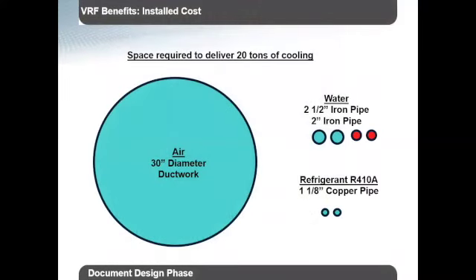So we think about, how is this possible? How is it possible that VRF can really be so much more flexible than a lot of the more typical technologies? We'll look here at a scenario where we're trying to deliver 20 tons of cooling to a space. If you're using ductwork to push air from a rooftop unit, you're going to need 30-inch diameter ductwork, or the equivalent in a rectangular, whatever that may be. That is a large, at least a main duct run that you can branch off of. But bringing that into a space can oftentimes be difficult.